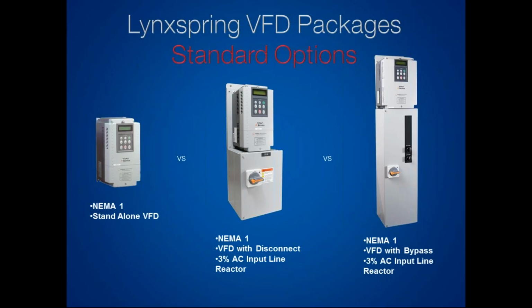Now, bear in mind, that bypass is just a starter, okay? So that bypass is going to run 100% on, 100% off, right? So you will be running your motor at 60 hertz, but in a lot of cases, it's better than not being able to run your motor at all, right? Another option with that bypass is to include an AC line reactor. Next slide.